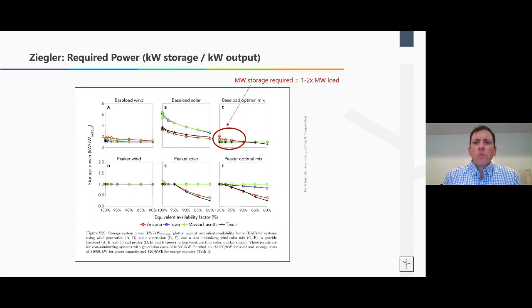Why would you need 2 megawatts of batteries to serve a 1 megawatt hour load, or a 1 megawatt of load? The answer is because you may only be discharging at a 1 megawatt rate, but you may need to be charging at a greater than 1 megawatt hour per hour rate. If you have solar with a 33% capacity factor and want to be 100% renewable, you're going to need at least 3 megawatts of solar for every megawatt of data center, and you need the ability to soak that up in the high, sunny hours.